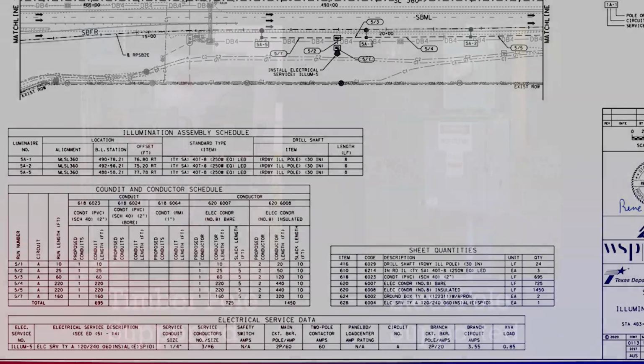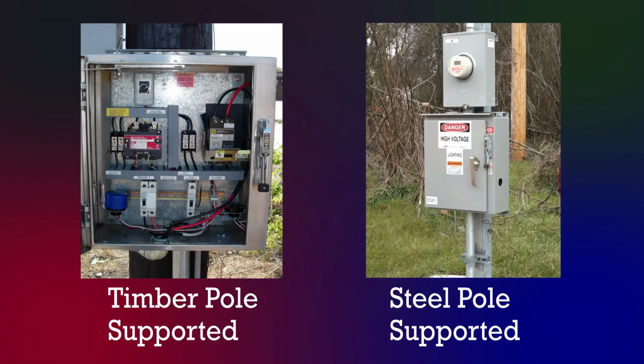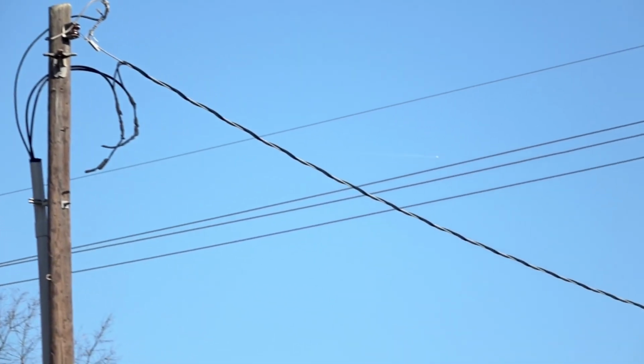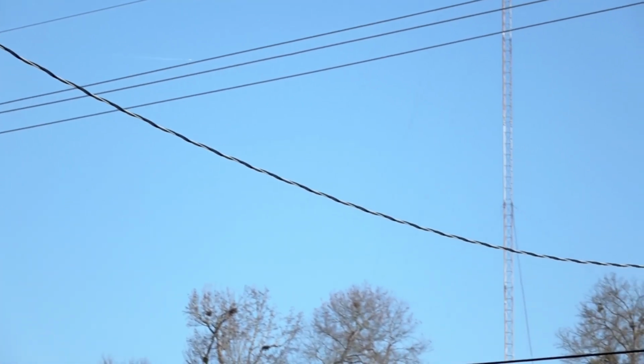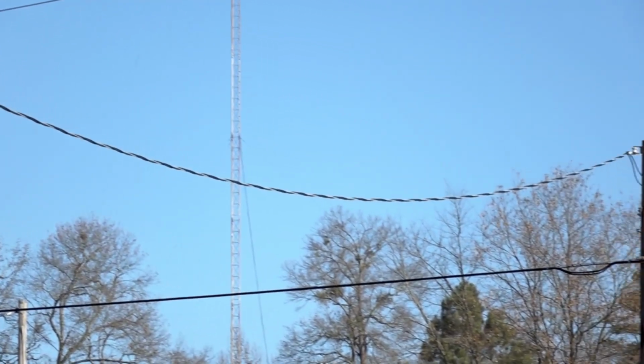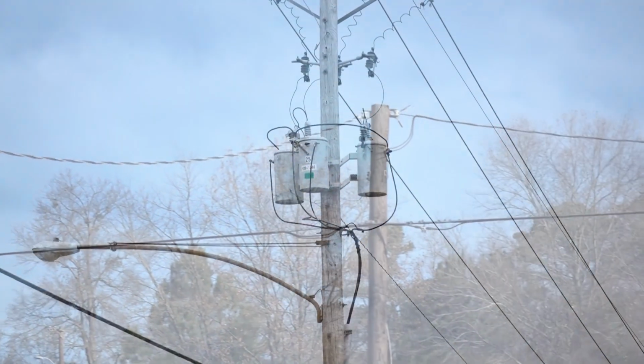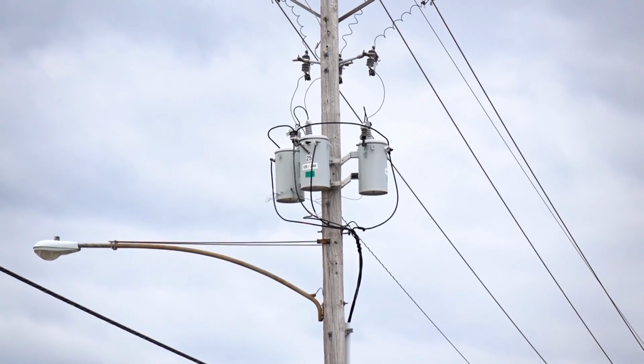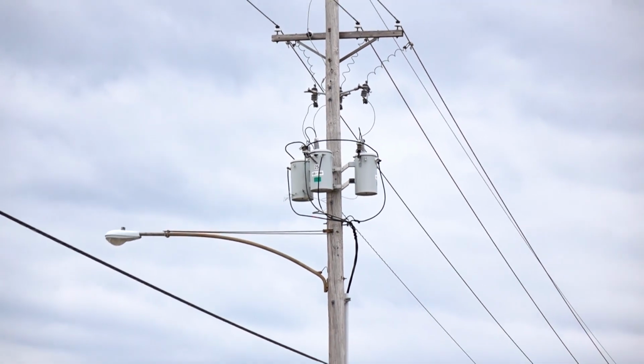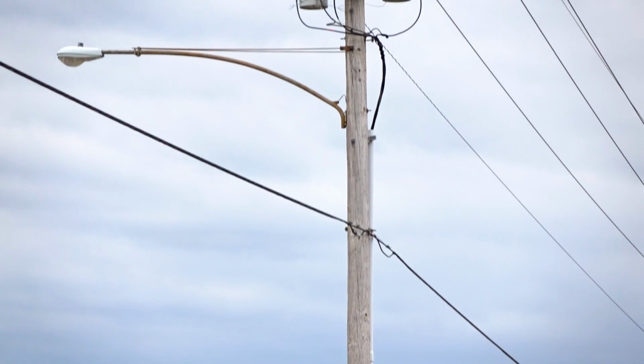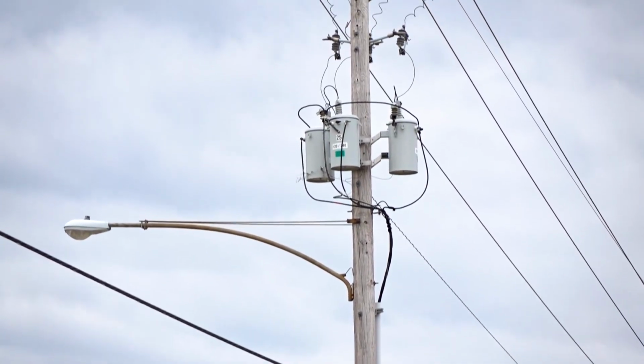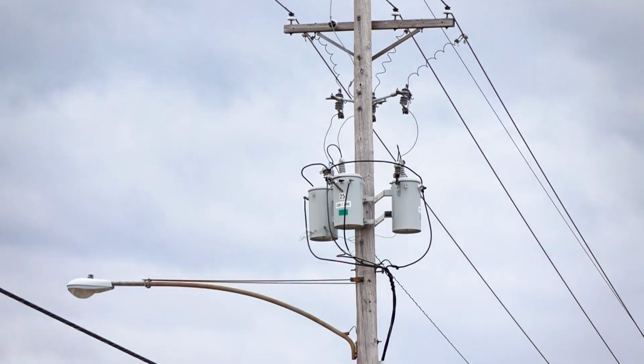The type of electrical service is independent of the kind of support structure the service may be mounted on. Nor does Type A designation determine the path taken by the conductors coming from the electrical utility supply. The three conductors going to the utility company transformer, the gray tank-shaped component mounted near the top of the utility pole, are called service drop conductors.